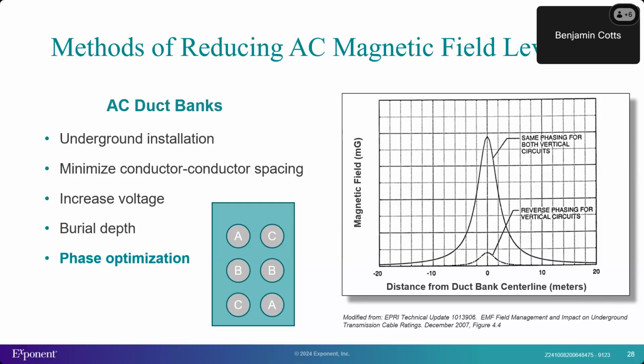But by far the most effective way of reducing magnetic fields is through a process called phase optimization. This diagram shows three different conductors labeled A, B, and C — the designation for the three phase conductors of an individual transmission line. When you have two different transmission lines in a duct bank, which is often the case for an offshore wind project, the orientation of those conductors can matter a lot.